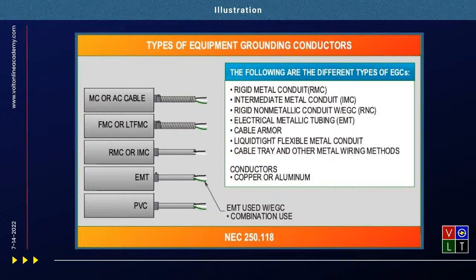So a lot of times inspectors try to pull that whole thing. The thing is, technically per code you can use the EMT as an equipment ground, but all the fittings have to be tight. That's why I showed the one that came loose at a hospital - that would actually be a violation even with a ground wire pulled through it, because under 517.13, if you're in a patient care area, you have to have both paths: the bonding path and the grounding path.